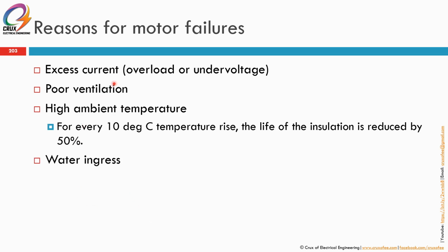So the reasons for motor failures are normally excess current, overload or under voltage. Excess current means higher current, then higher losses, I squared R, so more heating to the motor. This will damage the insulation and reduce the lifetime of the motor. It can also be due to poor ventilation, again related to heating, and high ambient temperature, if you're operating at a very high ambient temperature environment, 40 degrees or 40 plus degrees Celsius.